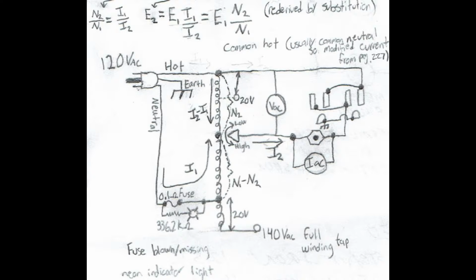It's clear from the picture that the right side of the outlet prongs are tied in common with the incoming hot line, which is located at the end of the coil, and the left side of the output prongs are connected together, and those are going to the Variac's wiper, which is currently positioned somewhere in the middle of the coils. Normally, I believe the roles of this are reversed so that we have a common neutral coming in that also goes to the output prongs instead of the hot that comes in as the common.